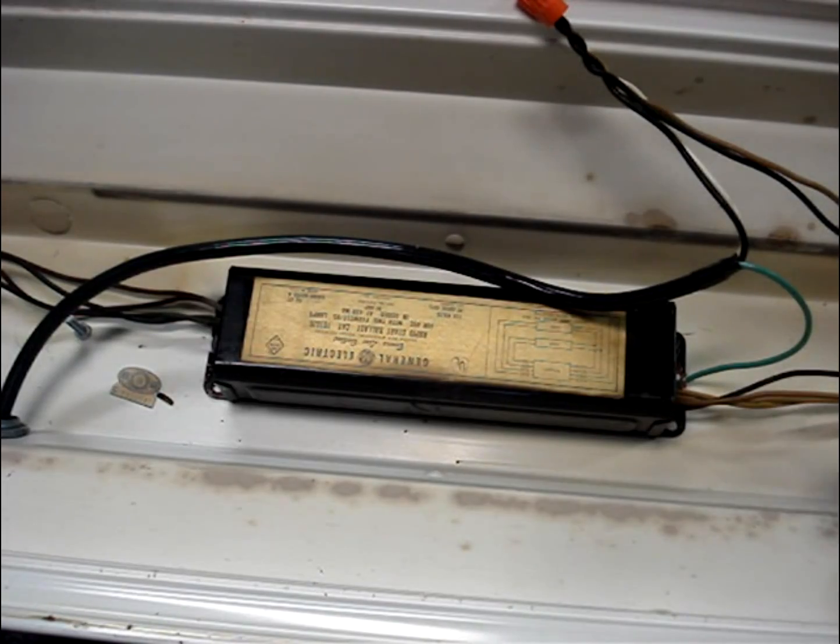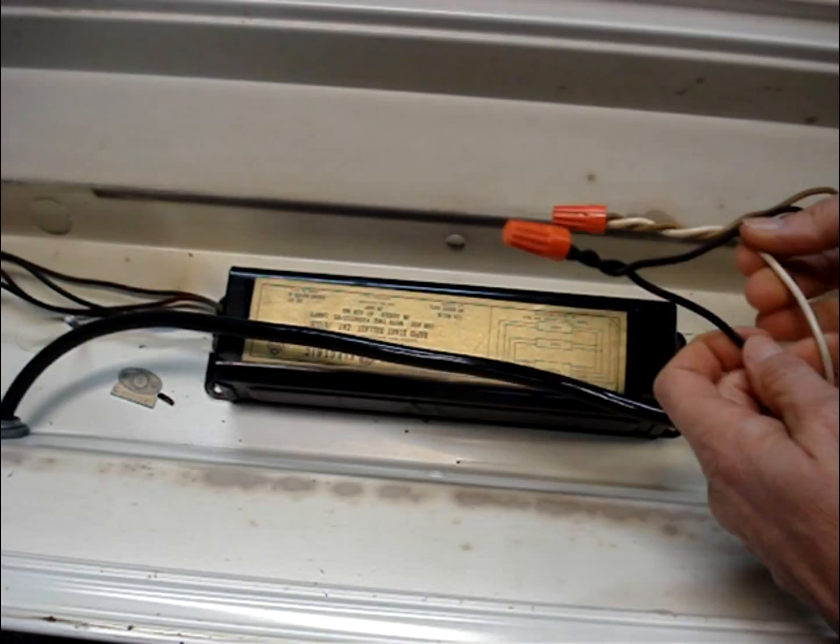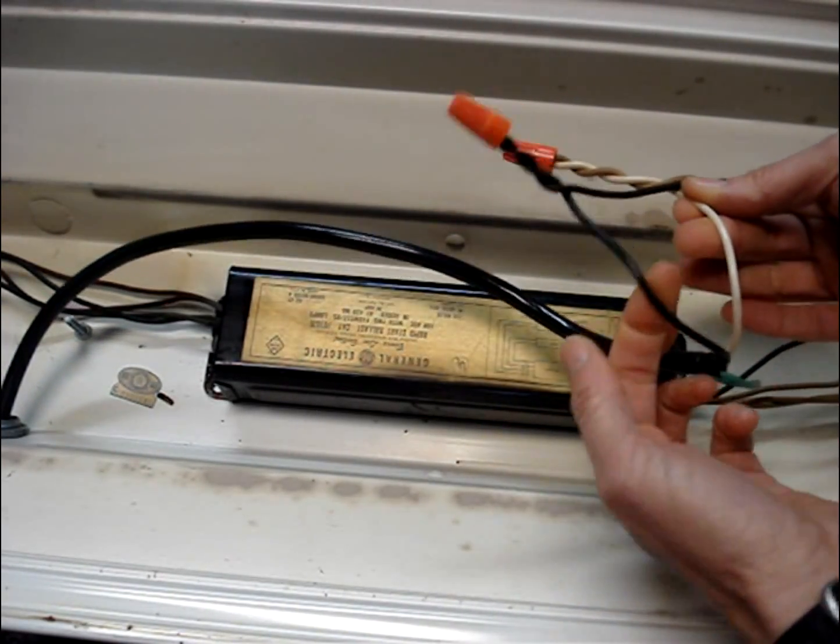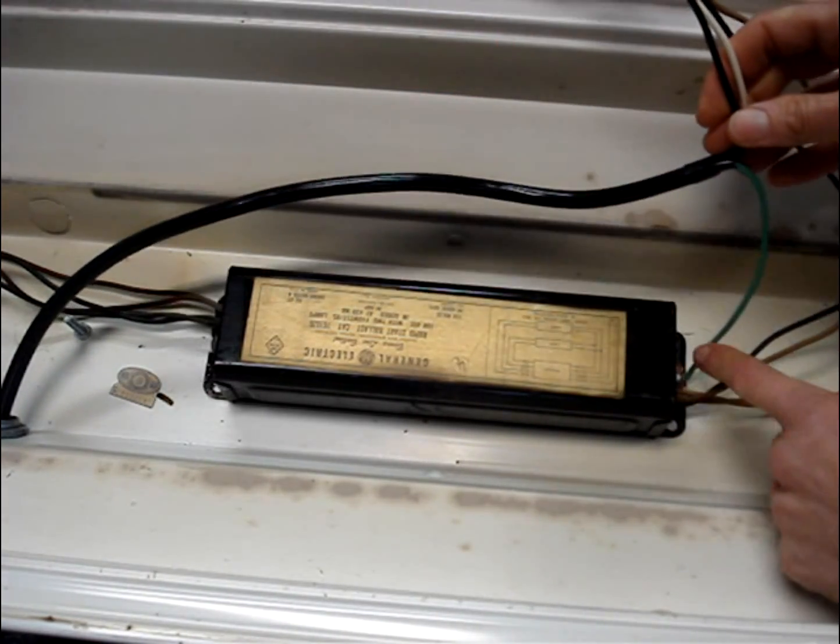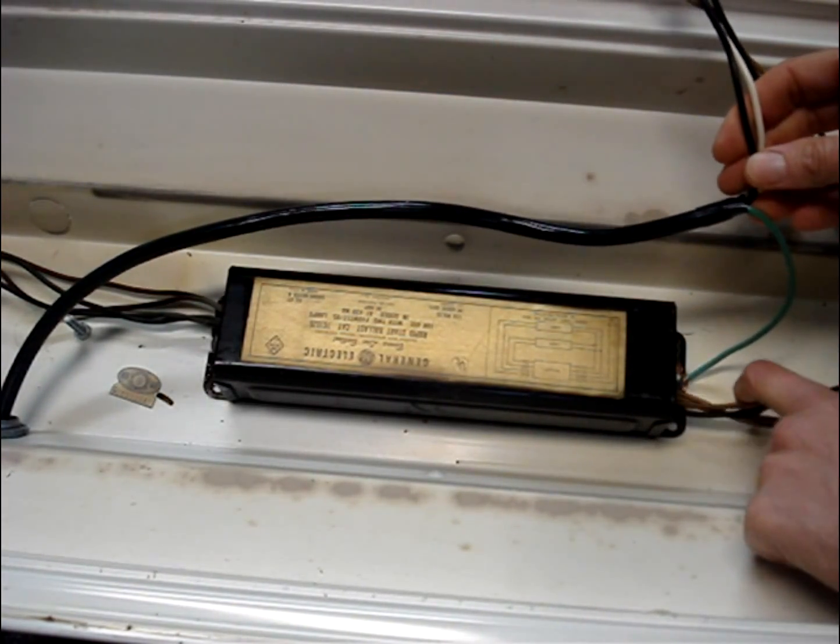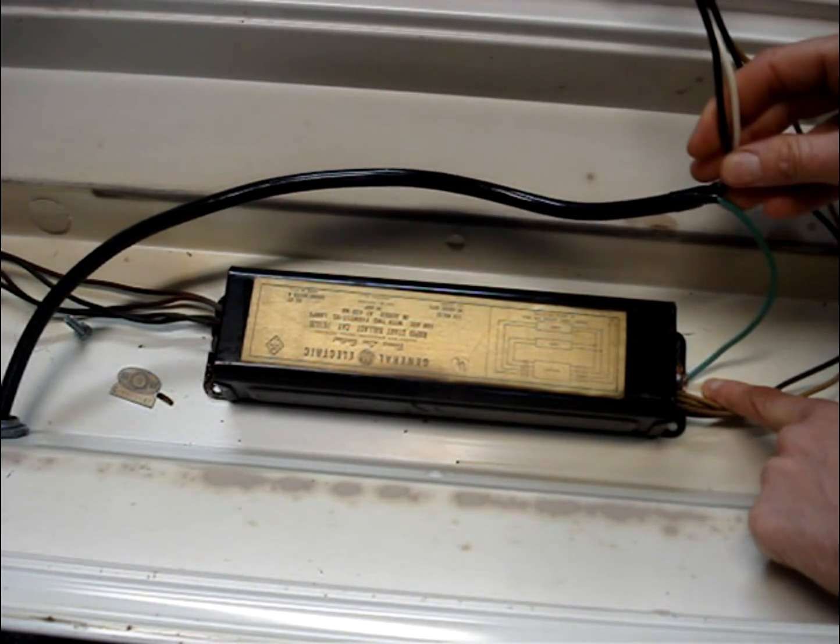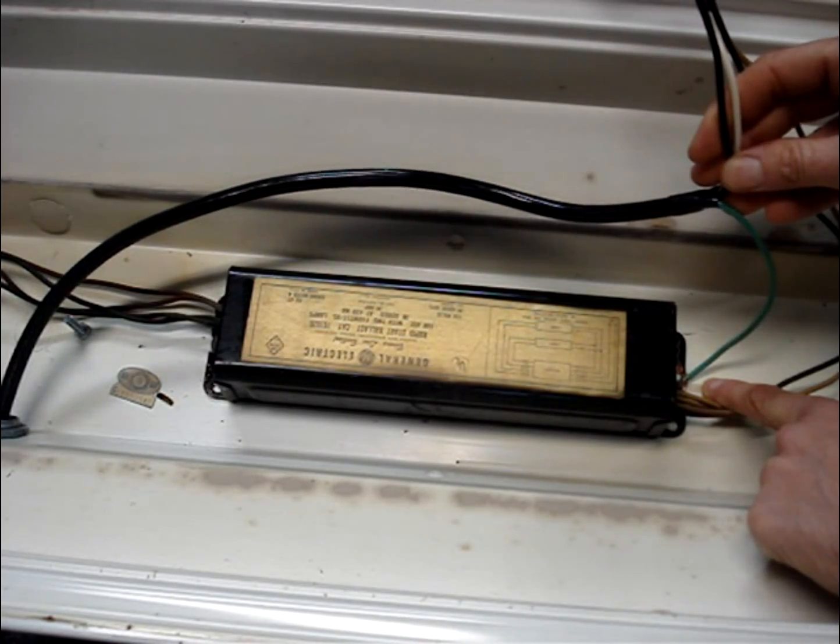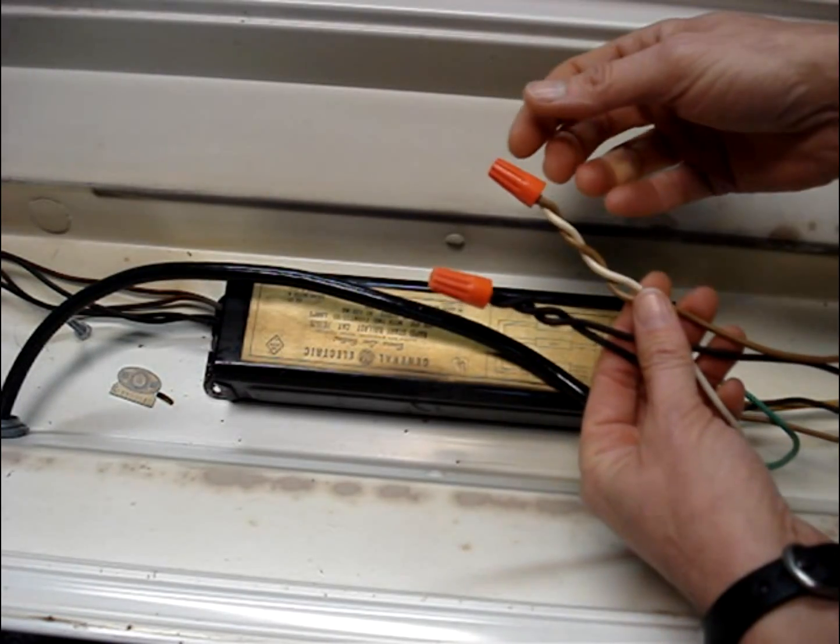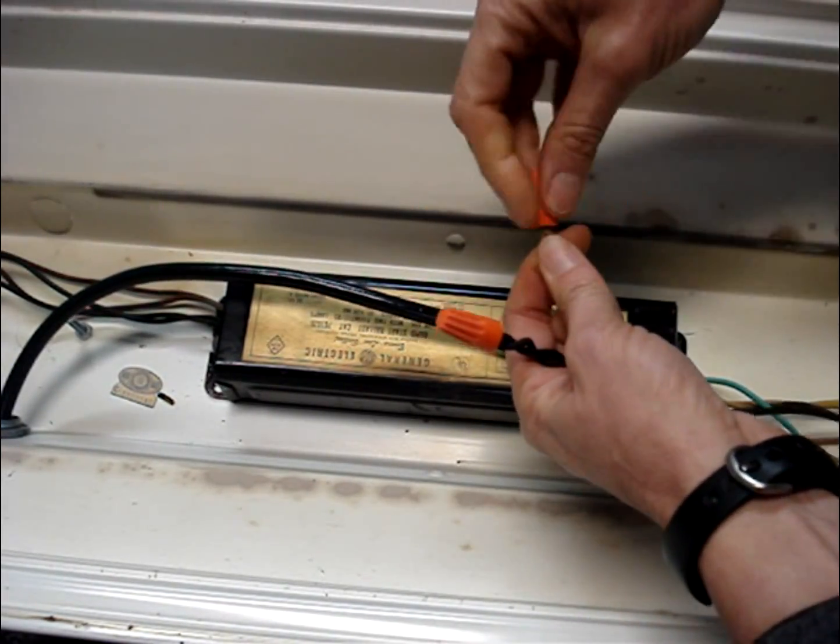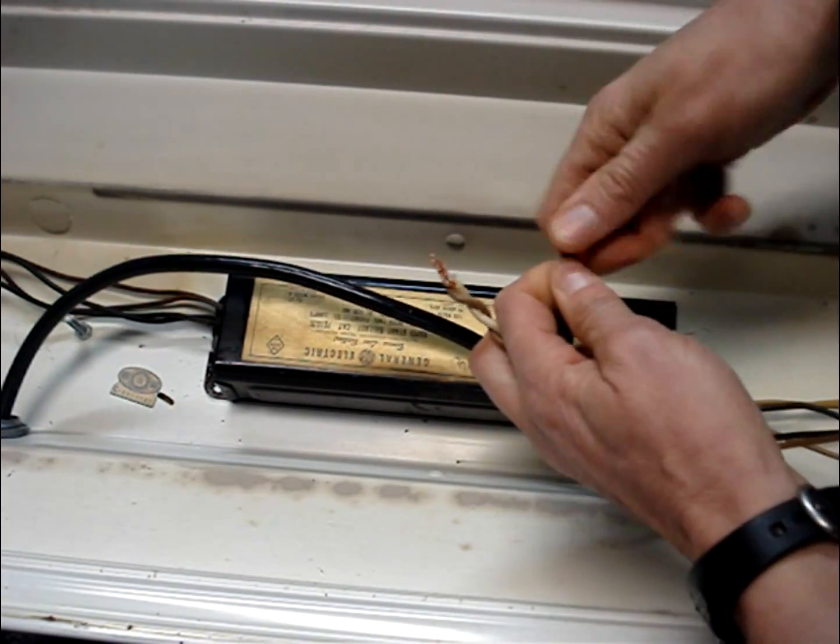Identify where the power feeds into the ballast and you should see a black wire for the hot, white for the neutral, and a green ground wire that should be fastened to the metal enclosure for the light. If you haven't already removed power to the fixture, you'll need to do that. Then disconnect the hot and the neutral wires from the ballast.